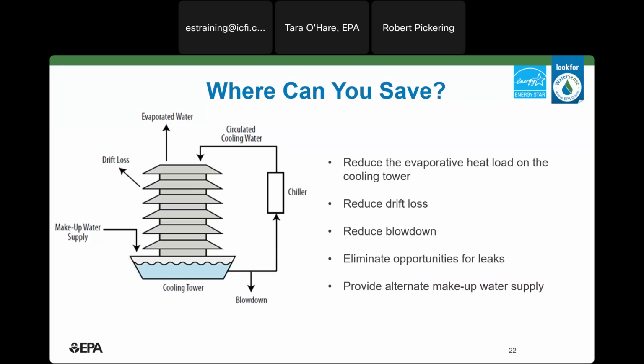So now that we understand what's going into the tower and what's leaving the cooling tower, we can understand where there are opportunities to save water. There are a few options. We can reduce the evaporation heat load on the cooling tower. We can reduce drift losses, reduce system blowdown. We can minimize the propensity for leaks, which are really just another form of unintentional blowdown. And then we can provide makeup water from a source other than city water.